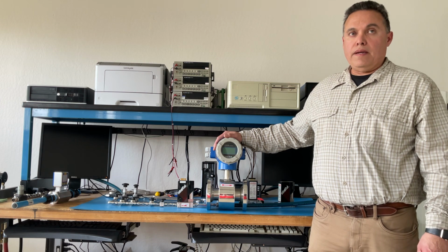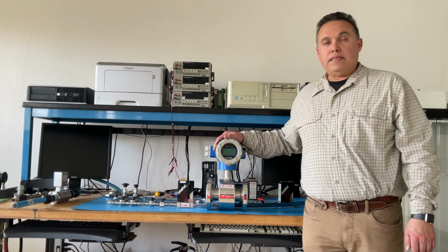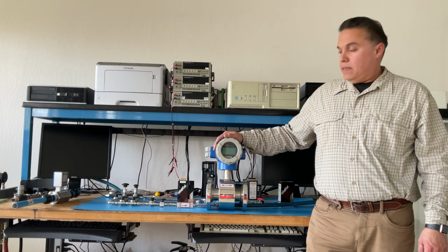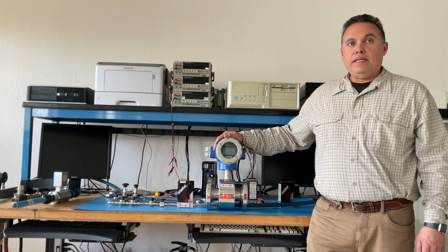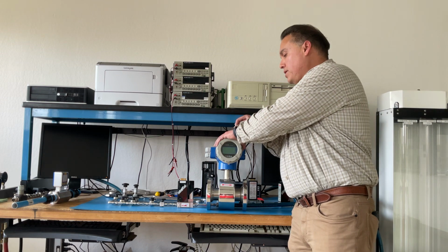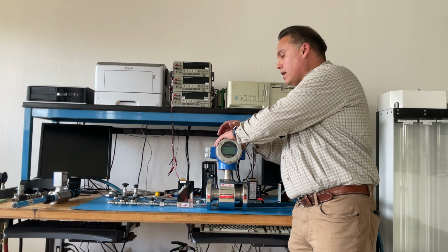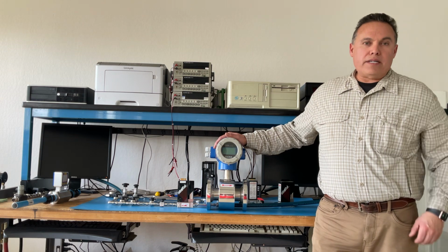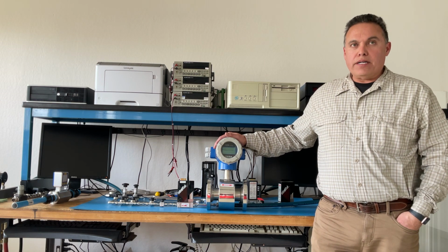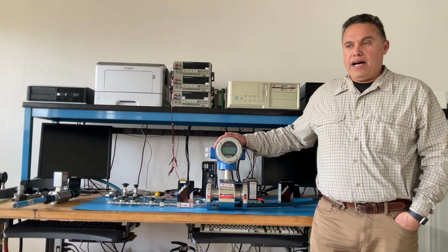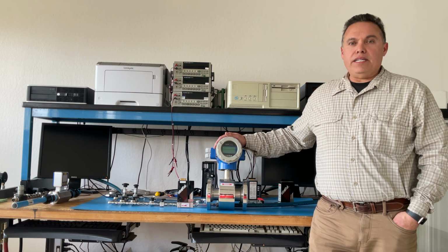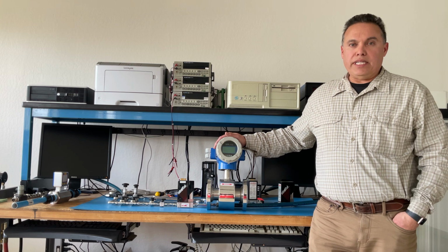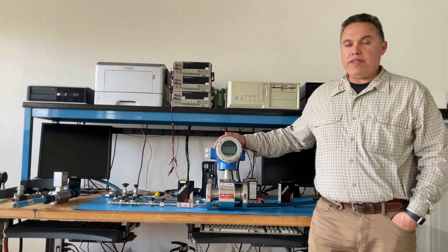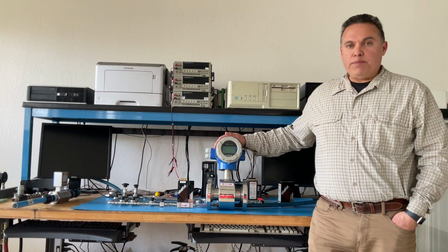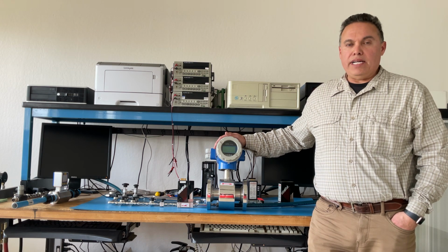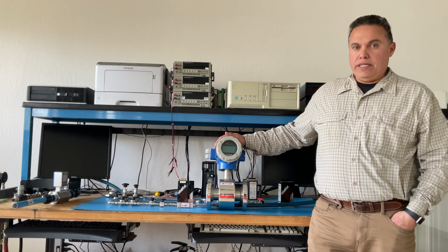The other questions I had were about common applications. We've talked about cement, and that seems incredible to me that you could use that for cement. What are some other common applications for this meter? Yeah, the most common is using it for potable water, sewage, dirty water, injection water if you're in oil and gas. Pretty much any kind of fluid that is electrically conductive, which is pretty much everything except for different types of oil, and deionized water has no minerals, so it can't be measured in this kind of meter.